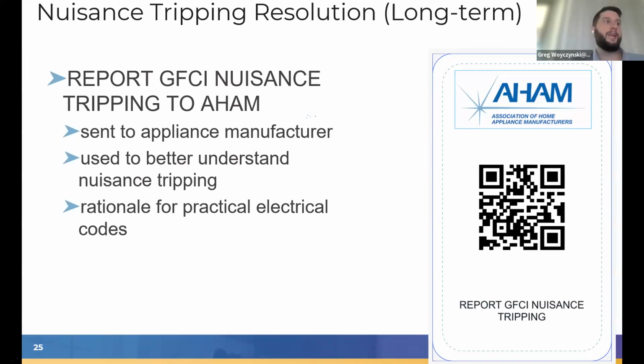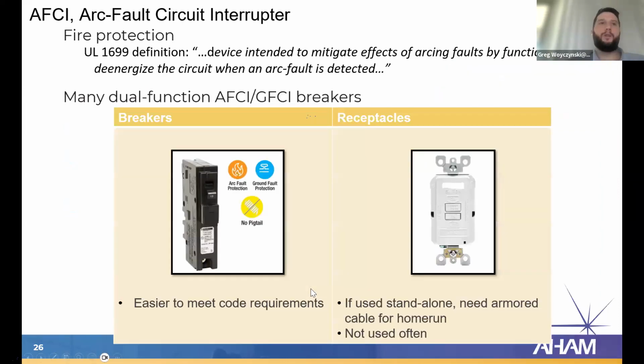Reporting and hearing about these cases is important, because when you talk to GFCI manufacturers and say, hey, we need to roll back these NEC requirements, they'll say nuisance tripping isn't happening. You're making this up. This is the appliance's fault. When we know, according to the UL study and testing that's been done, that's just not true. Okay. So let's talk quickly about AFCIs.